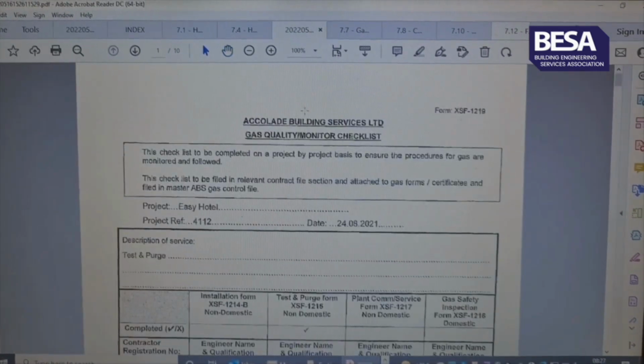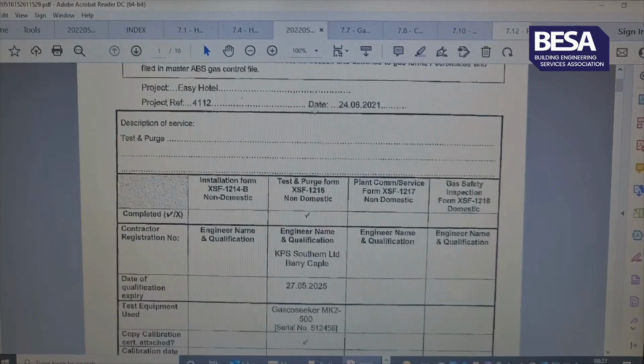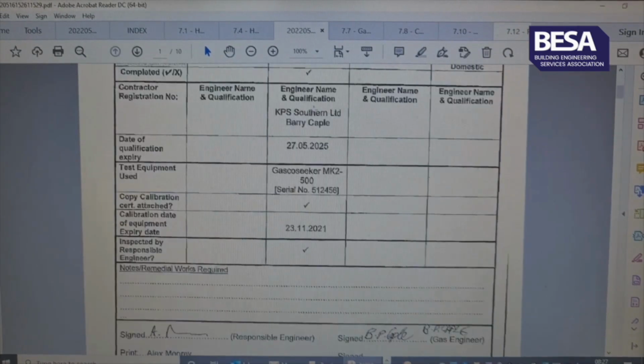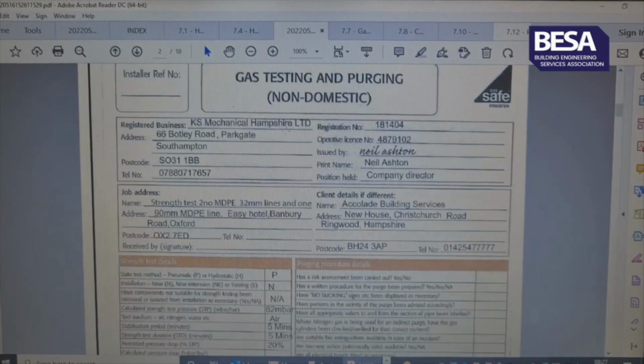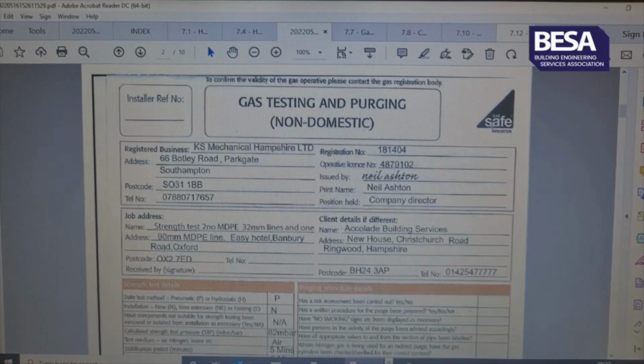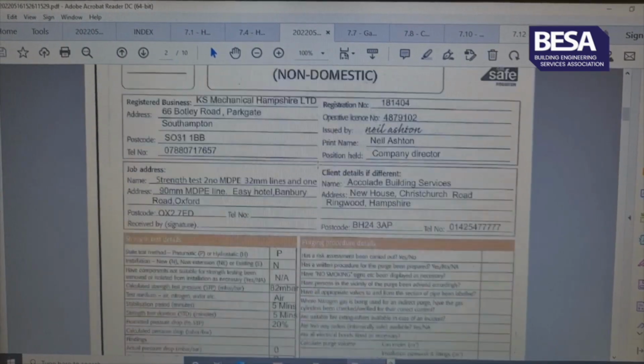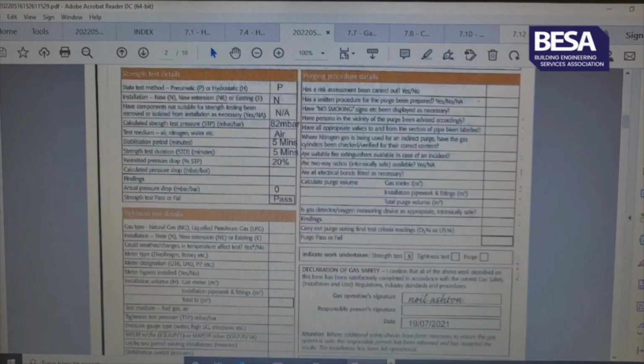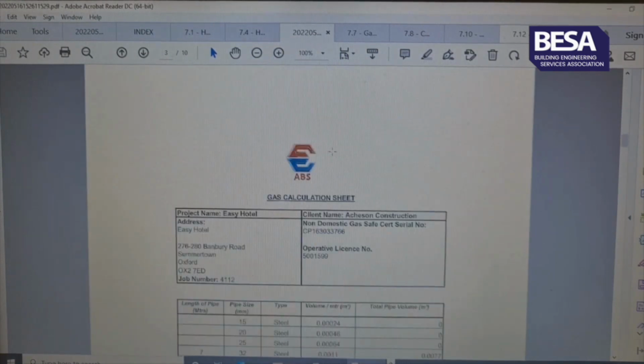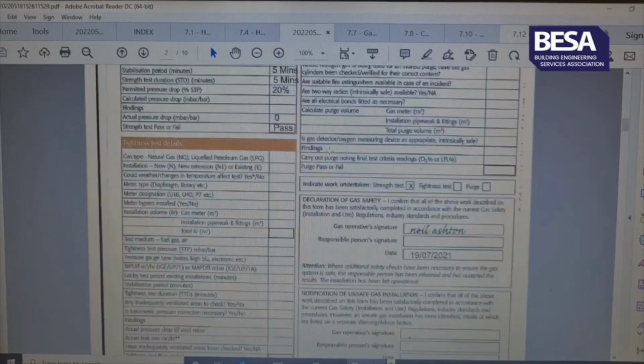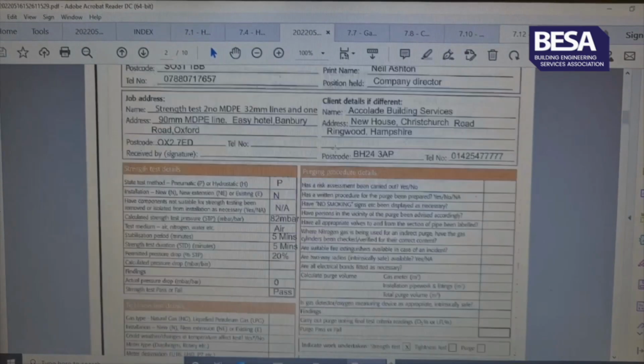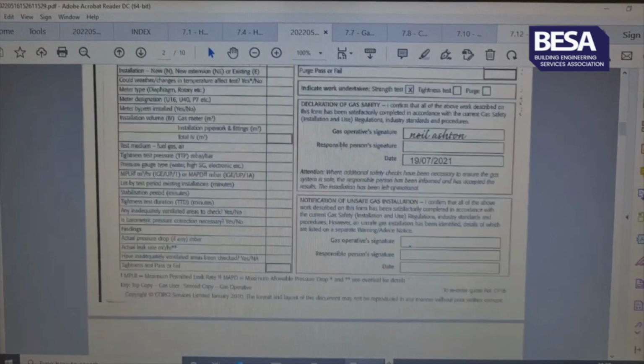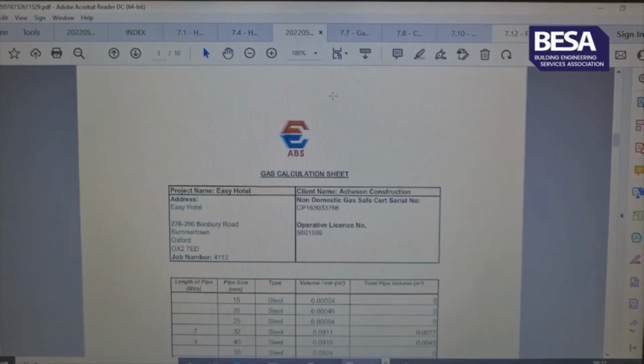Next up we're going to look at is the gas certificates. Two companies carried these out on our behalf, both Gas Safe registered. This is the test for the 32mm MDPE as it came in for future use into the plant room. And then here, that was just literally a strength test. There's no meters actually connected to this section yet, so there's no test and purge being carried out.